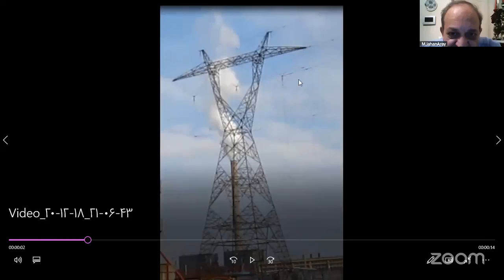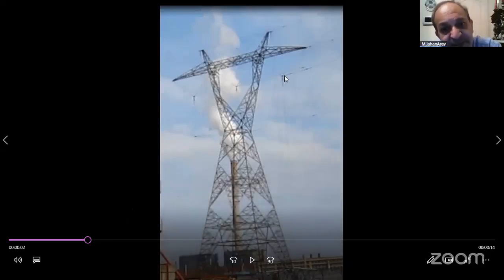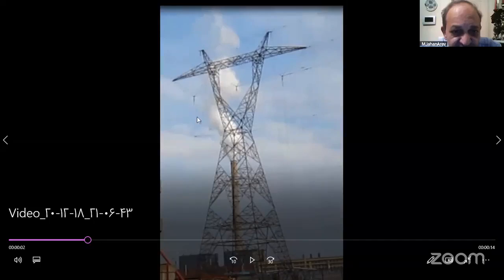This direction, if you can see my mouse pointer, is the transverse load, caused by wind on the conductor and also the degree of line deviation. The vertical loads are obvious, caused by the dead loads of conductors and also the shield wires. And in this direction, normal to the tower, we have the longitudinal load.